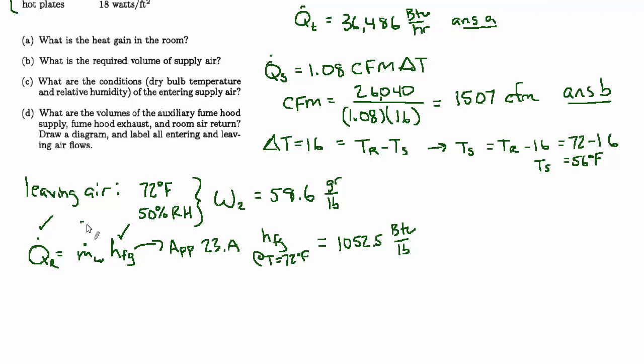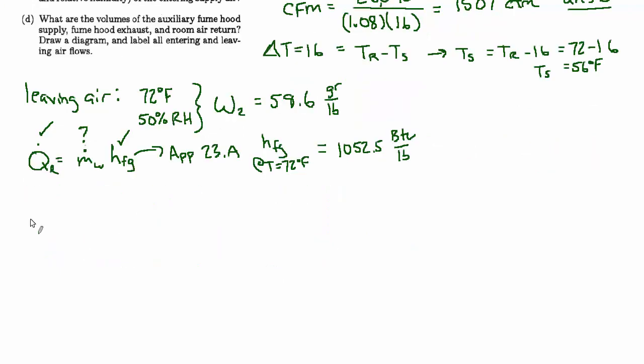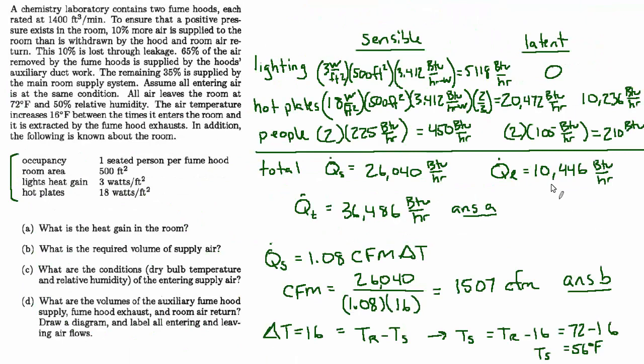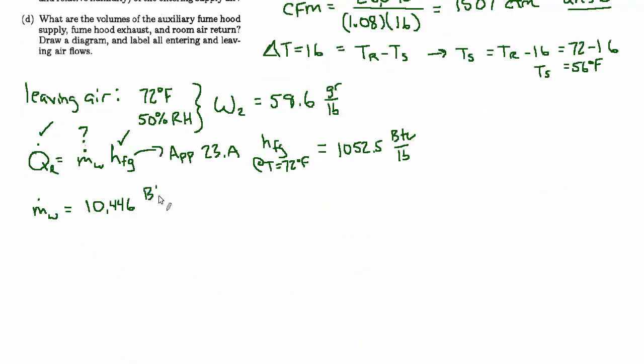So we know HFG at the temperature we care about, and we know the latent load, we can find the mass flow rate of water. That's the water vapor being added to the air by this latent load. So let's solve for m dot w. The latent load we calculated before, we said it was 10,446, and that's BTU per hour, divided by the latent heat of vaporization, 1052.5 BTU per pound. BTU's cancel out, we're going to end up with pounds per hour, and the value is 9.92.